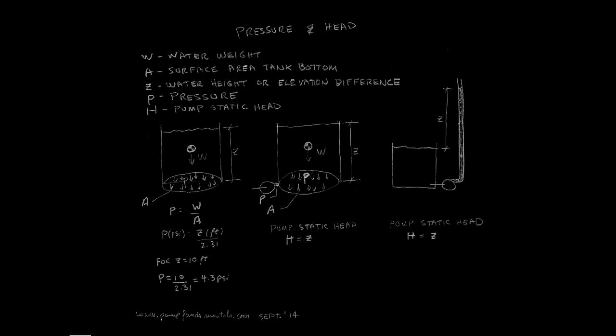You may ask: since we always need a suction tank, why not just use the head at the pump discharge to indicate its capacity? Because the pump manufacturer has no idea what size tank you will put on the pump suction or what the water level will be in that tank. We calculate the head required to make our system work — including friction, static head, and equipment pressure drops particular to our installation. The manufacturer gives us the amount of head the pump can produce for a given flow rate between the discharge and suction connection, independent of any particular installation.